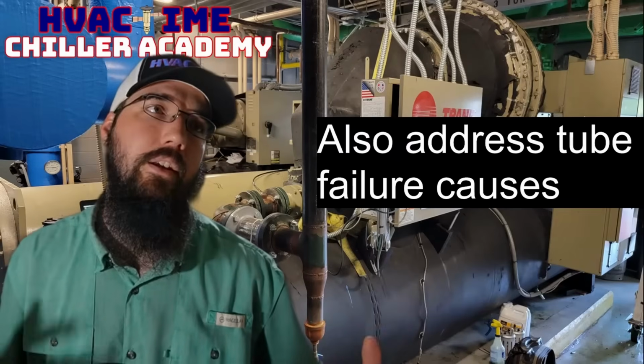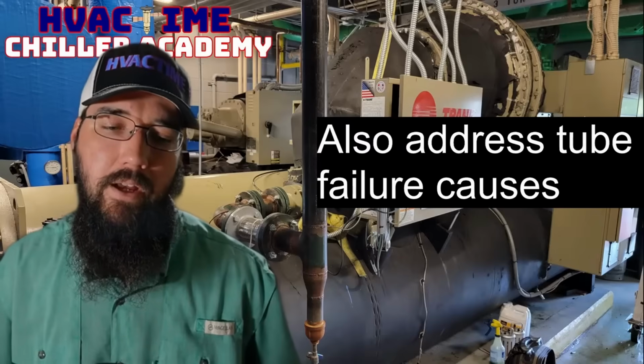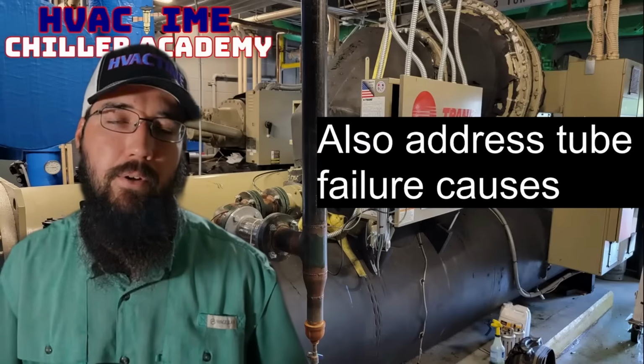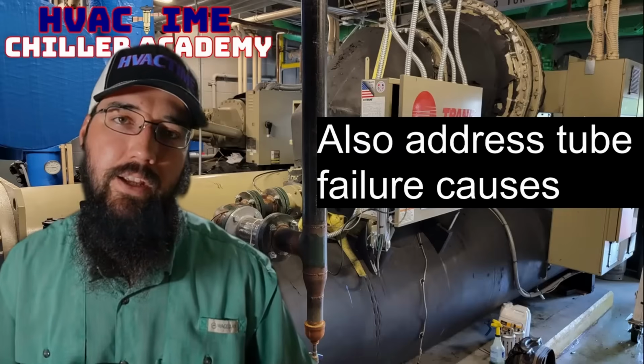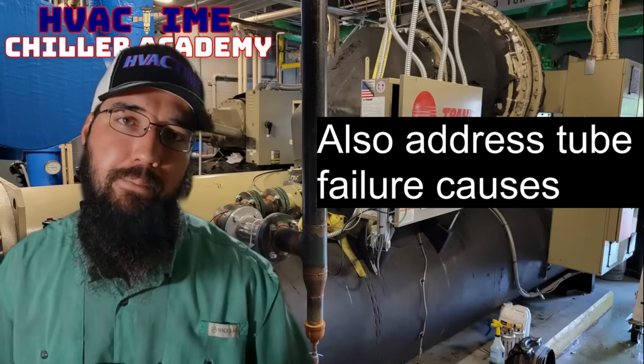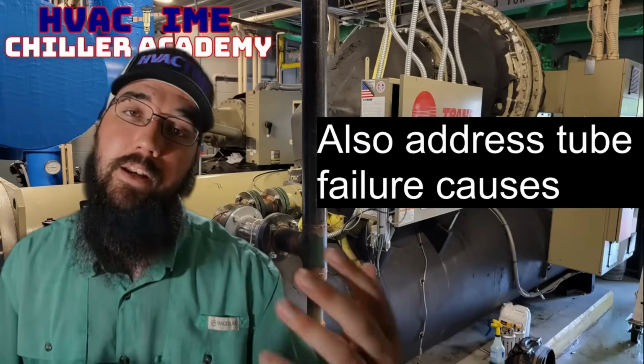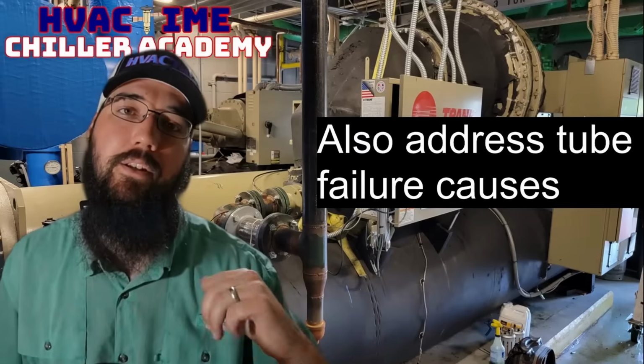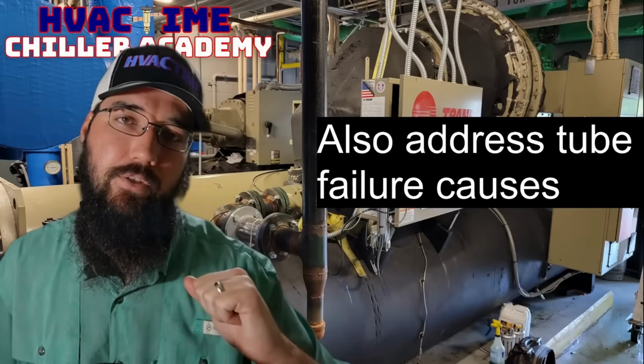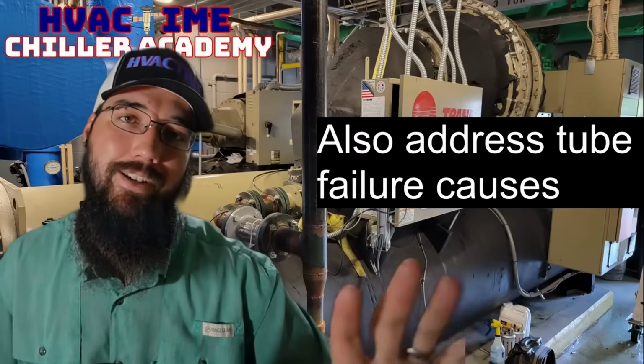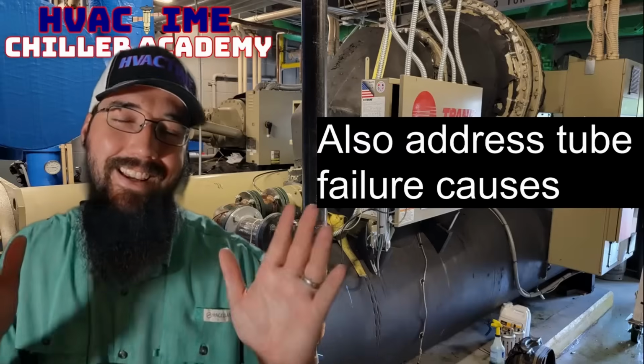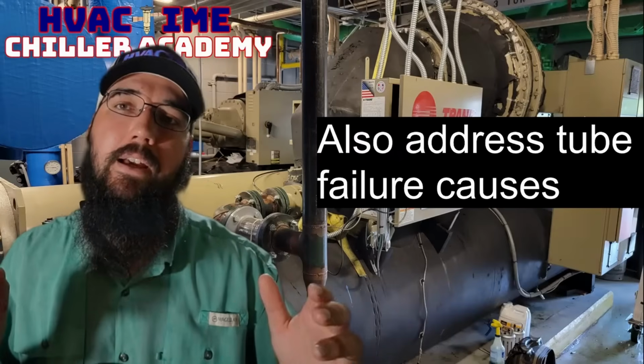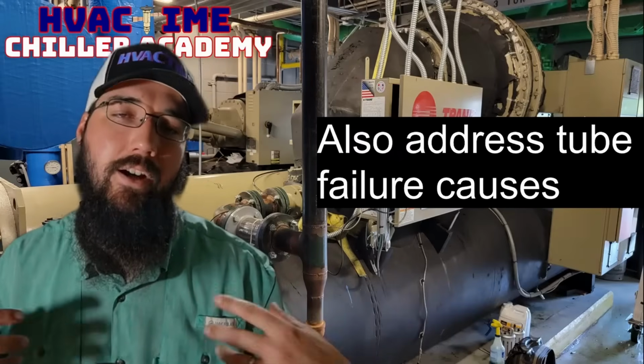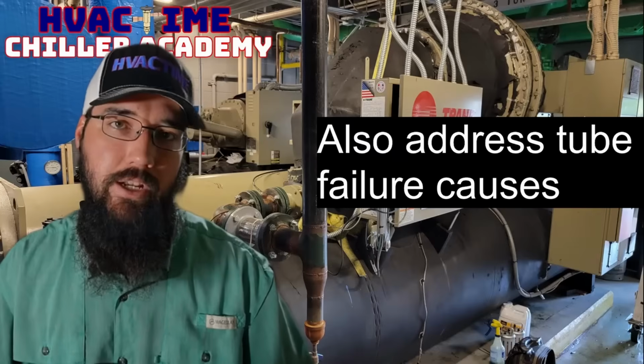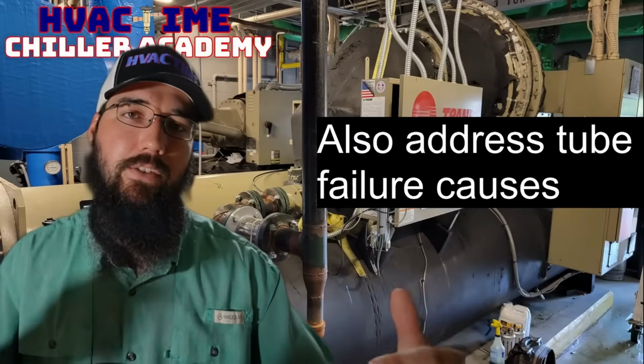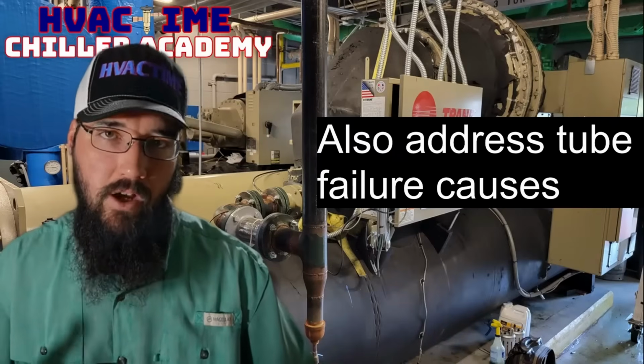So the 515 by Loctite would be a popular choice for this. Put a little 515 on it, and you're going to hammer that plug into that tube and ideally stop it. Now, before you put the plug in, it is recommended to use some nitrogen or something and try to blow that water out of there and dehydrate that tube ahead of time, so that if a failure did end up happening, whatever moisture is in there isn't able to get into the machine and vice versa. Plug your tube sheets. That's one of the most common ways about it.